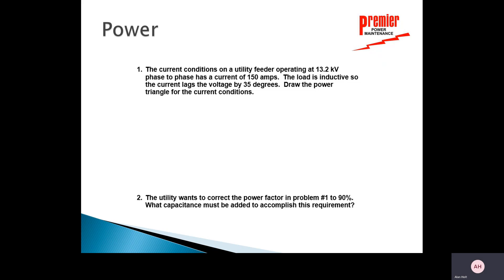To finish up, let's talk about the power factor triangle, or power triangle. We'll look at an issue from a utility or customer perspective to understand how to improve power factor. We know that we typically have inductive loads as a customer, and to correct power factor we need capacitors. The scenario: a utility feeder operating at 13 kV phase-to-phase with a current of 150 amps on the phase. The load is inductive, so the current lags by 35 degrees.